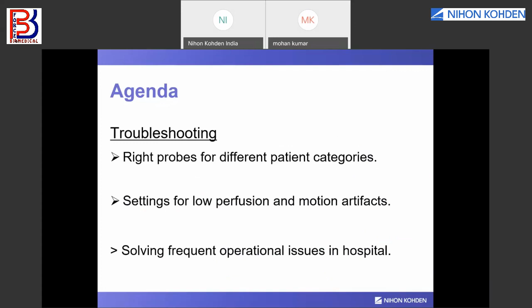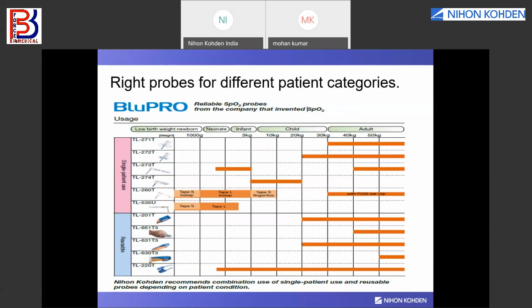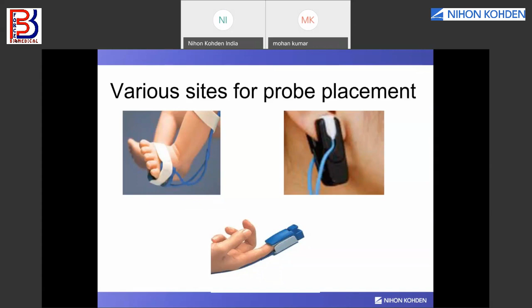As you know, there are various sites to measure SpO2 and various kinds of probes available according to the birth weight, the neonate, the size, the weight, like infant, child, adult. As you can see in the chart, it has various probes, reusable probes as well as single-use patient probes. And it all depends on the patient weight, from 1 kg or below 1 kg to 50 kg or above 50 kg. And there is a recommendation to use those probes according to the weight of the patient. There are various sites as told by Mr. Mohan Kumar: a foot for neonate, the earlobe for clip kind of probe, and the finger probe. It depends on the patient condition and what problems we face during measurement of SpO2.